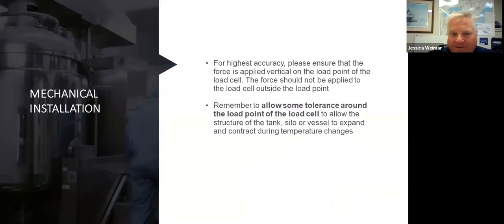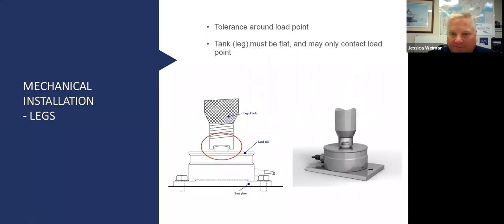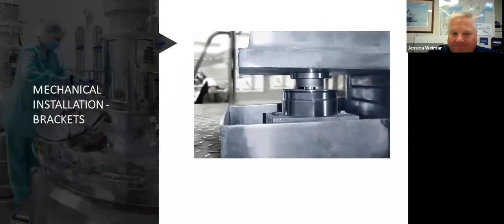I'm going to back up here, there we go, back to installation. In a perfect installation, we do want to make sure that the force is applied as vertically as we can, and we want to keep the load cells as far outboard on the load as possible. What does that mean? If I've got a square tank, I want the load cells as close to the corner as I can, the actual weighing portion of the load cell. I don't want them in the middle of the tank, all right? And remember, we have to maintain some tolerance around there for expansion and contraction, all right?